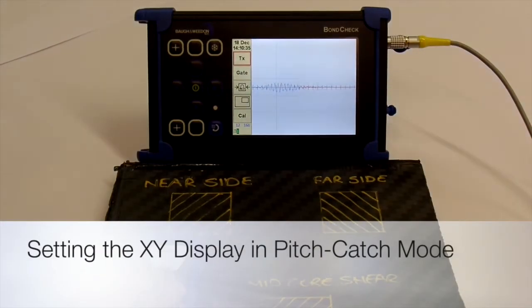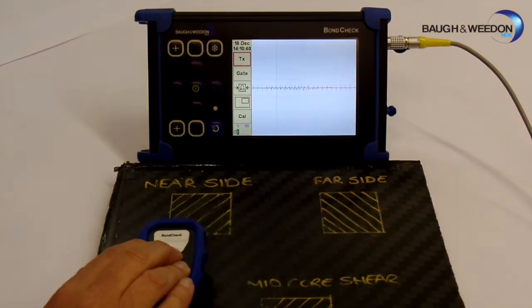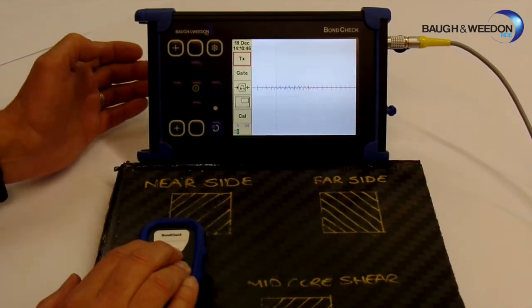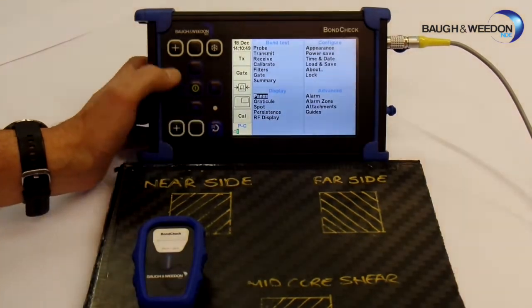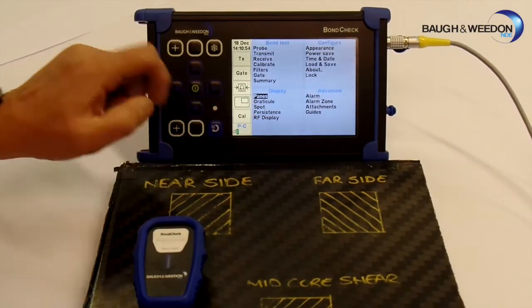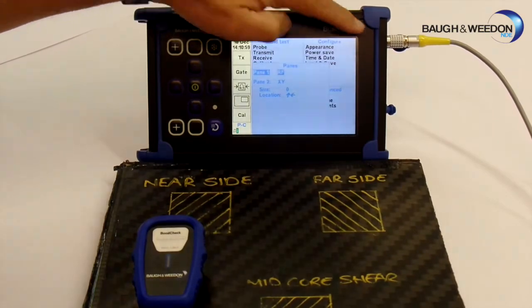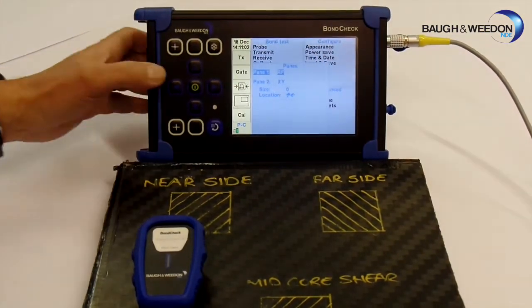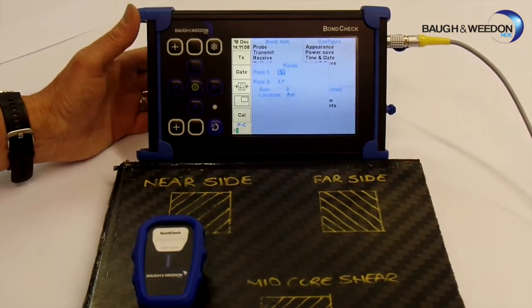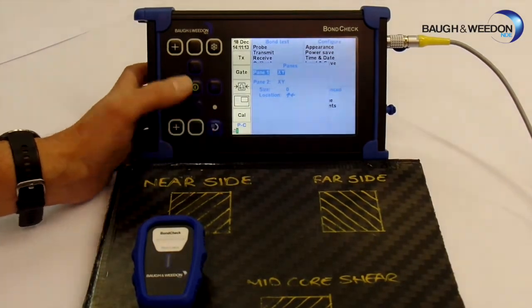Some people like the RF display, some people don't. So we have other options, and another option here is the XY display, commonly known as the flying dot. So the way we get to the flying dot display, select the backspace to go to the menu, go down to the panes icon, select panes. And you can see pane 1, which the big pane is, is on RF. So if we select that, we can change that to spectrum XY. We want XY for the flying dot, selected that, come back out again.